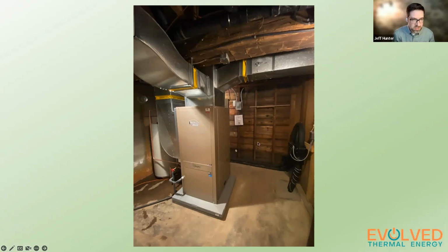Now there's also hydronic heating systems. Like I said, water is the best way to transfer energy, and that's why hydronic heating is so popular—things like in-floor heating are low temperature heating systems. Older existing homes that use high temperature baseboard rads or cast iron rads require more consideration, because heat pumps don't like high temperatures; they work best at a low temperature rise. So when looking at systems like that, we need to understand the building load, how well the envelope of the construction performs, how much heat the house loses room by room, and what heat emitters we have in each room, and how to adapt those emitters to a lower temperature system. They're more complex in their analysis and approach, but certainly anything is possible.